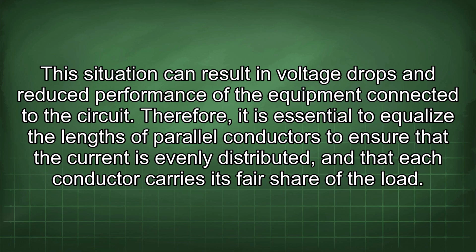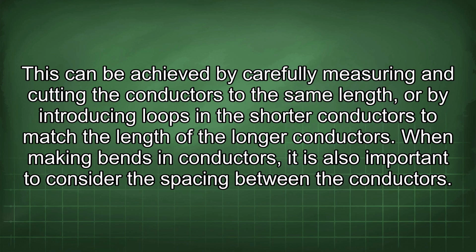Therefore, it is essential to equalize the lengths of parallel conductors to ensure that the current is evenly distributed, and that each conductor carries its fair share of the load. This can be achieved by carefully measuring and cutting the conductors to the same length, or by introducing loops in the shorter conductors to match the length of the longer conductors.